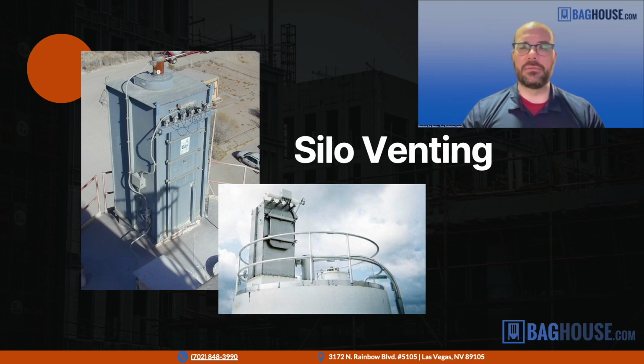So a lot of problems with silos, with loading, unloading, these kinds of things, a lot of these come from not having the bin vent either sized correctly or maintained well. So they're definitely an area when we go and do inspections and system audits, it's definitely an area where we see a lot of plants lacking and where they can make improvements.